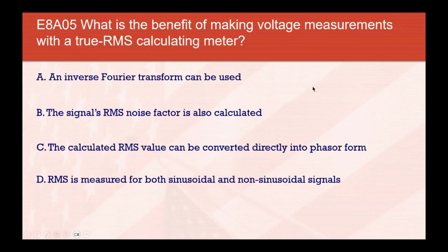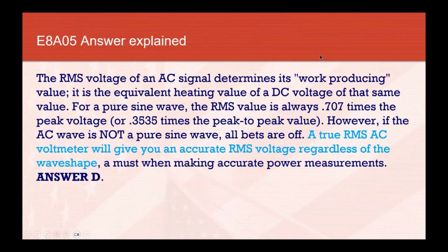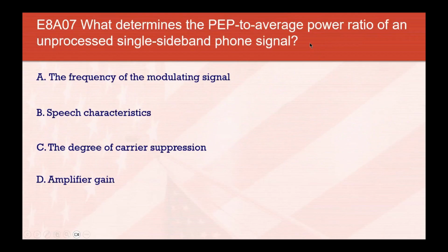Benefit of making voltage measurements with a true RMS calculating meter: RMS is the equivalent to a DC voltage as far as heating value is concerned. On a pure sine wave, we can calculate it with 0.707 times the peak value. However, if it's not a sine wave, we need a meter that will do the calculation for us, built into the meter.